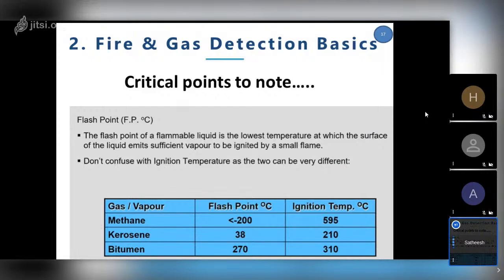So all these hydrocarbon materials have their own temperature. In gas, it is called auto ignition temperature. In liquid, it is called flash point. What we are trying with instrumentation is that our instruments should never dissipate heat, and ensure this temperature is not hitting these points. That's very important. So now you can relate to the hazardous area and the equipment while selecting. These temperatures play a major role. The fuel, what exactly is the cause, and what are the temperatures? We always try to define that and design accordingly.